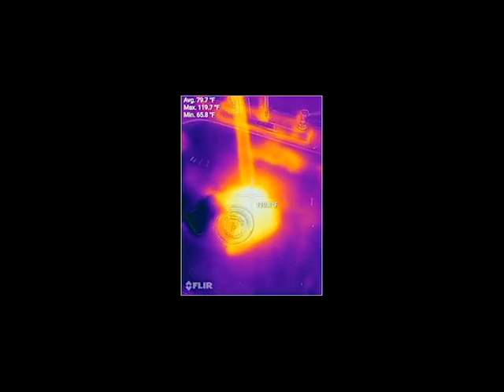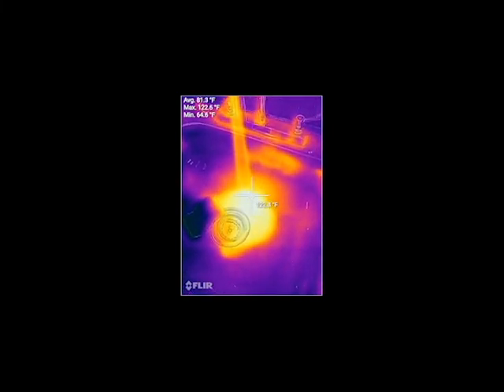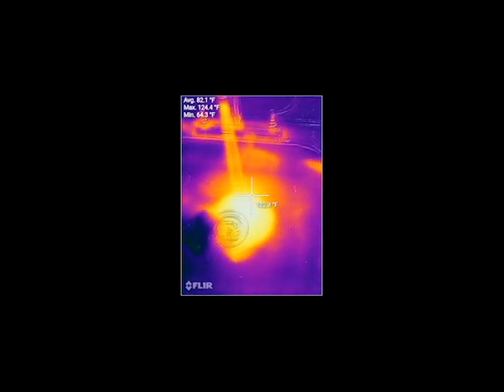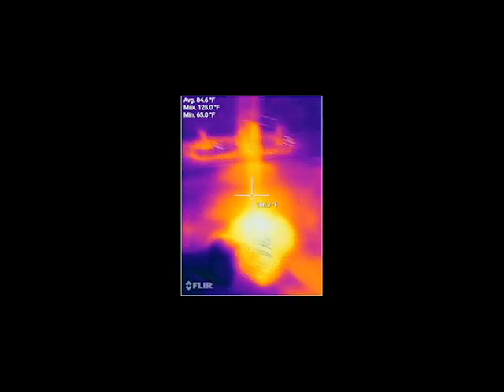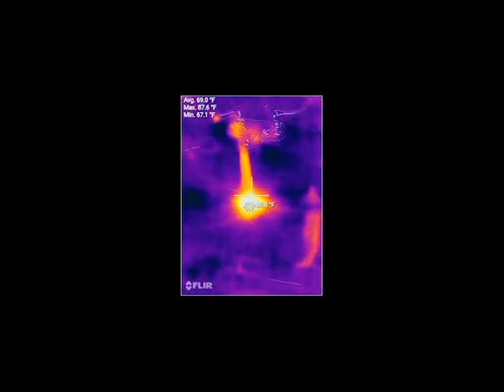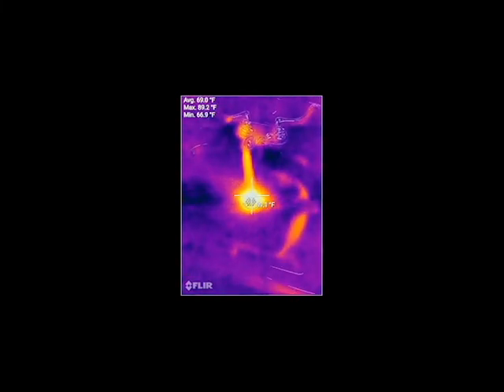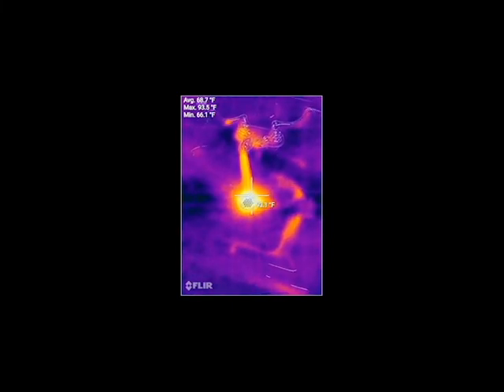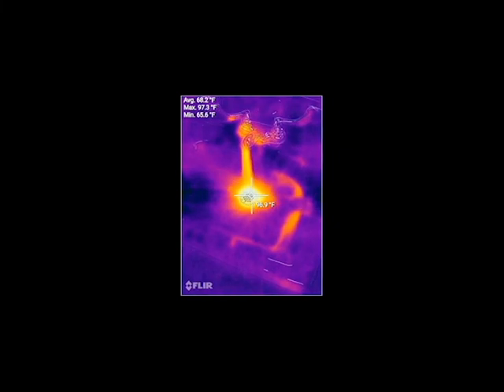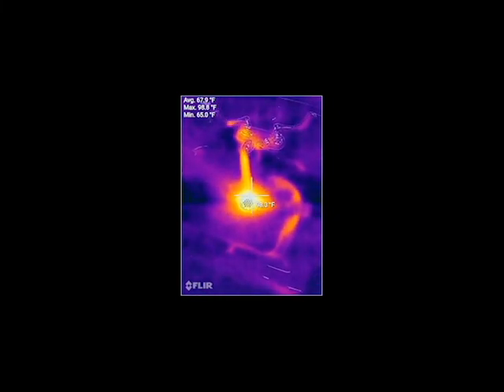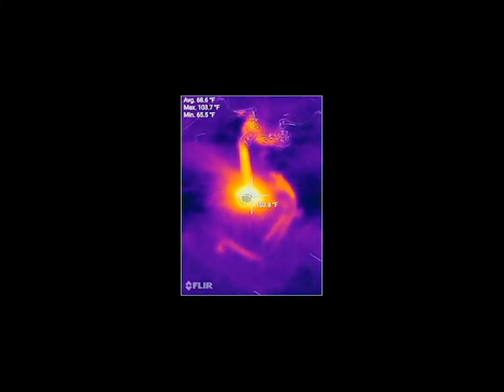The hot water itself, the sink is working just fine, even though at the janitor's sink the faucet is not working. Here we have 123 degree hot water coming out. Although, it's early in the morning, time to tap took a little while. This is the bathroom fixture. It is warming up. It did take a little while, but it is getting there. We may have a circulation pump issue because both the kitchen and the public bathroom have a significant time to tap. It might not be just because it's first in the morning, because I'm sure people have been using the bathroom since it's open.